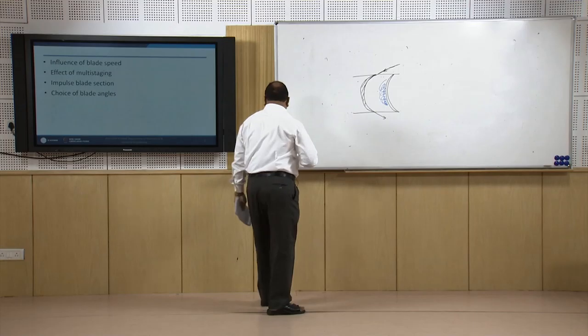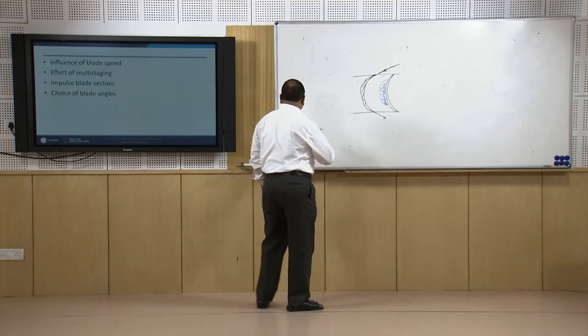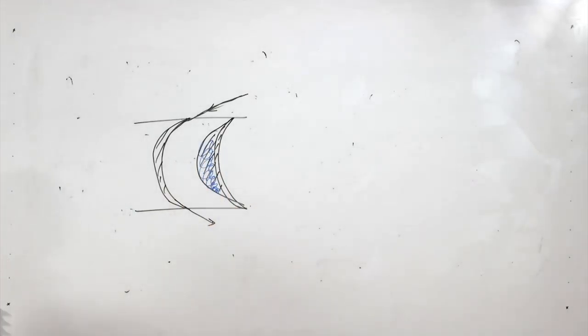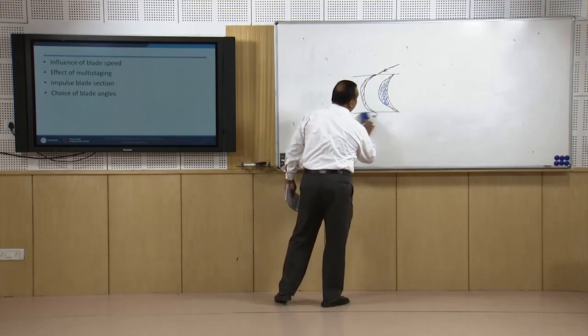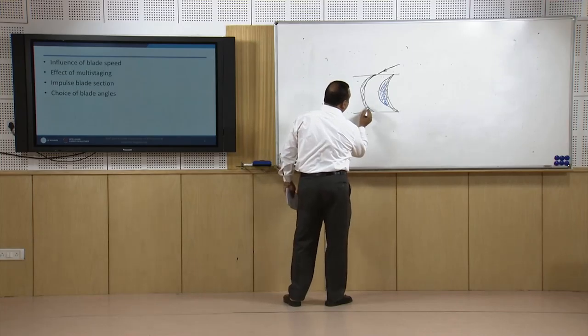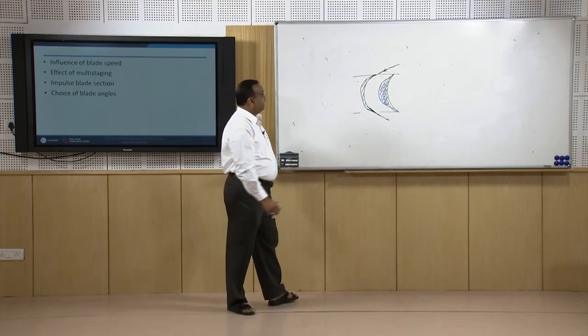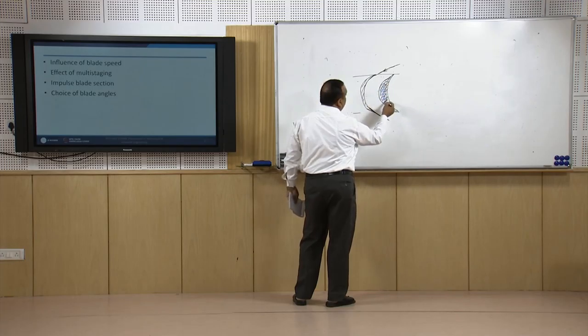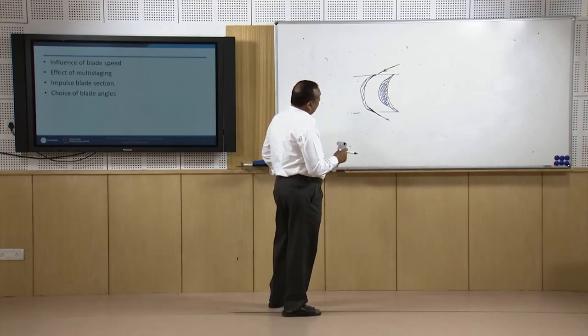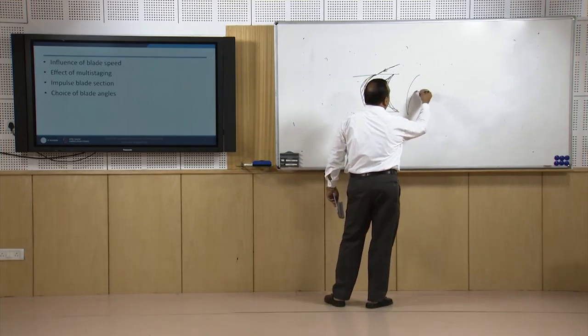To overcome this, profile-type blades were introduced. The suction side was extended to eliminate turbulence near the convex surface and improve blade performance. In some cases the exit side was also extended to give proper direction to the outgoing steam. This profiling of impulse turbine blades significantly improved turbine performance. In reaction turbines, airfoil-type blades are used, which will be discussed in detail when we cover reaction turbines.